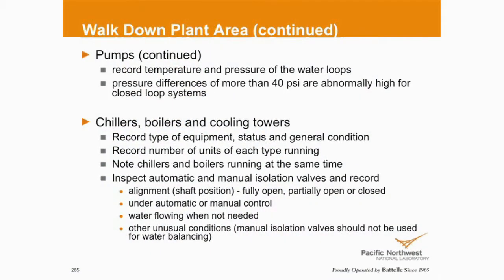So again, it's a huge opportunity with BAS systems to look at that. The vendors are putting that data into their equipment. You can pull it out if you're integrated, or you can do it on your own with your BAS system. Automatic and manual isolation valves. We talked about this earlier, but we do find this a lot, where people are using the manual isolation valves as a balancing valve. On VFD-driven systems, it's not a good idea, but we consistently see that. It's an opportunity.